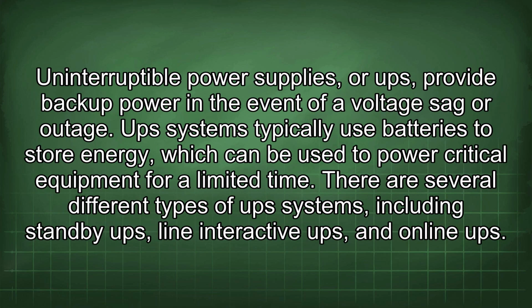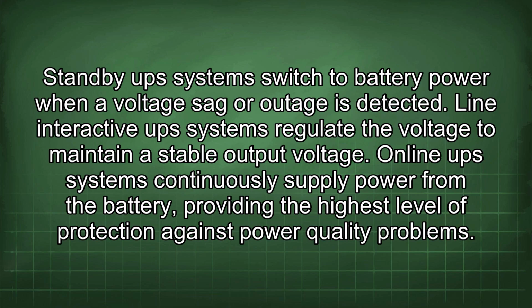Uninterruptible power supplies, or UPS, provide backup power in the event of a voltage sag or outage. UPS systems typically use batteries to store energy, which can be used to power critical equipment for a limited time. There are several different types of UPS systems, including standby UPS, line interactive UPS, and online UPS. Standby UPS systems switch to battery power when a voltage sag or outage is detected. Line interactive UPS systems regulate the voltage to maintain a stable output voltage. Online UPS systems continuously supply power from the battery, providing the highest level of protection against power quality problems.